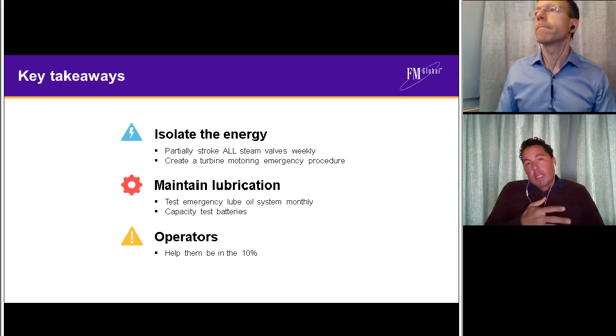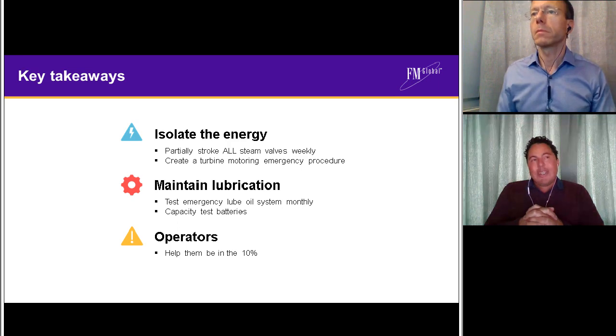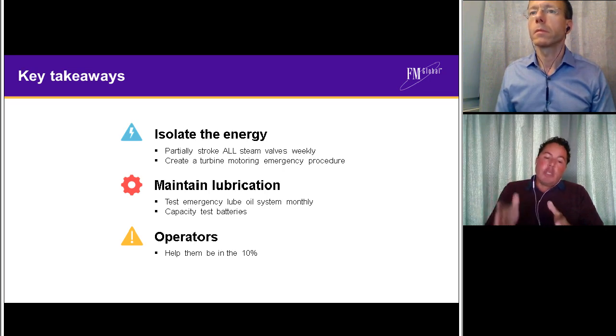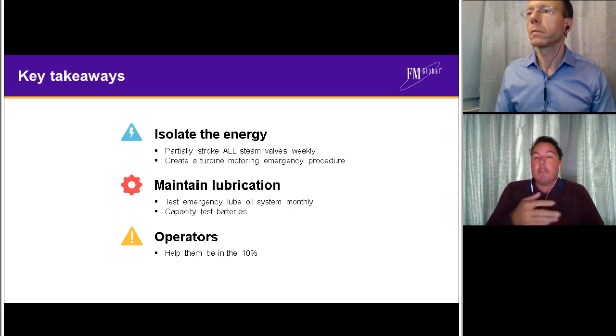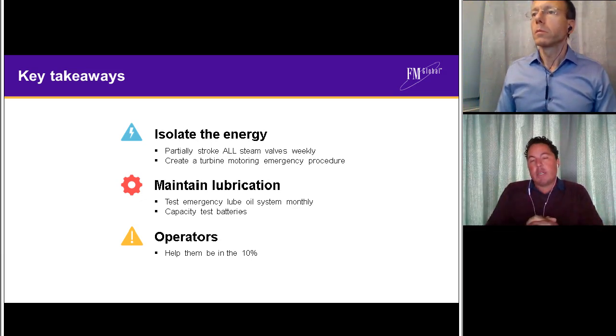Again, Adam, I suppose linked to an extent to the previous question, there is scope for condition-based monitoring. So, for instance, if you're looking at valve overhauls where we have a minimum frequency of 5 years, but you would need to make that shorter and be doing it more regularly if, for instance, there were chemistry excursions and you had concerns about scaling, or if there had been any evidence of sticking when you were testing valves.